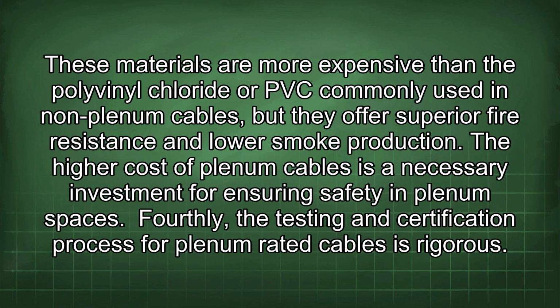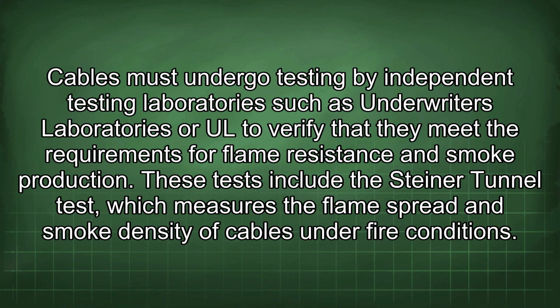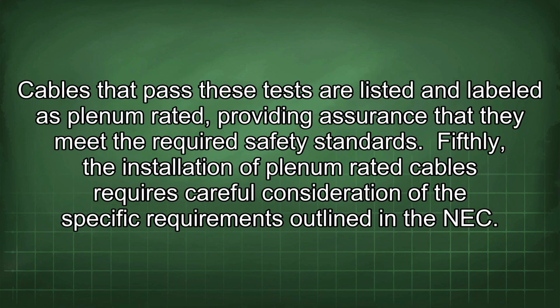Fourthly, the testing and certification process for plenum-rated cables is rigorous. Cables must undergo testing by independent testing laboratories such as Underwriters Laboratories, or UL, to verify that they meet the requirements for flame resistance and smoke production. These tests include the Steiner tunnel test, which measures the flame spread and smoke density of cables under fire conditions. Cables that pass these tests are listed and labeled as plenum-rated, providing assurance that they meet the required safety standards.